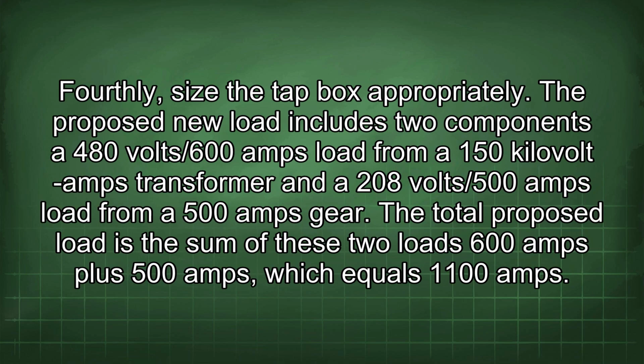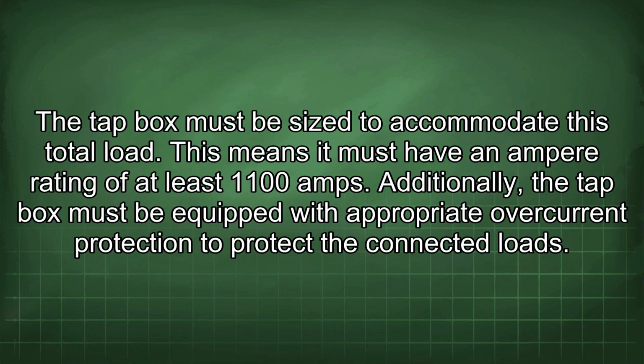Fourthly, size the tap box appropriately. The proposed new load includes two components: a 480 volts/600 amps load from a 150 kVA transformer and a 208 volts/500 amps load from a 500 amps gear. The total proposed load is the sum of these two loads, 600 amps plus 500 amps, which equals 1100 amps. The tap box must be sized to accommodate this total load. This means it must have an ampere rating of at least 1100 amps.